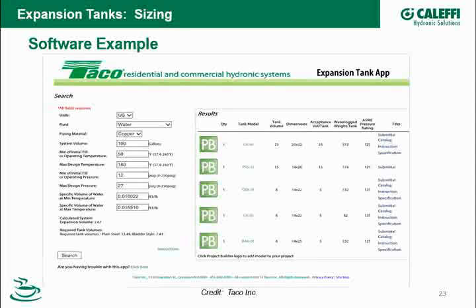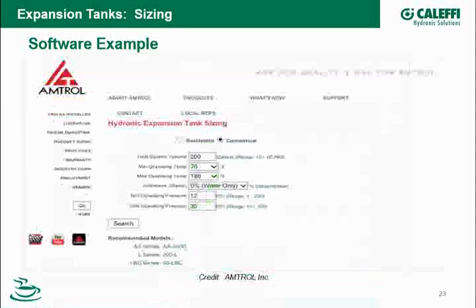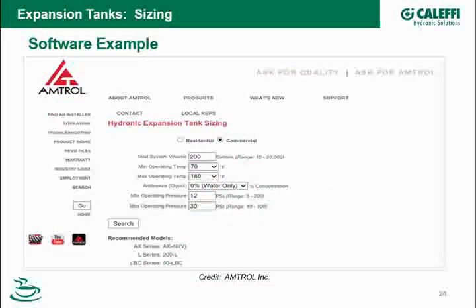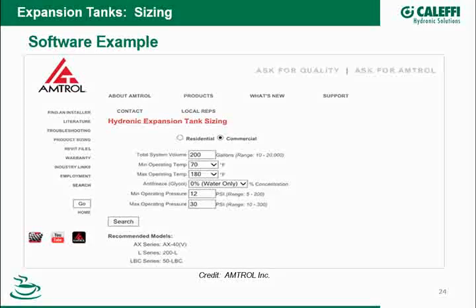Okay. Here's one from Amtrol. Bell & Gossett has one. I believe Wessels has one. So there's a lot of great resources out there to size the expansion tanks without having to actually go through doing the calculations longhand. And these software packages all have the information that we pretty much have been discussing so far. I need a total system volume, a minimum operating temperature, and a maximum operating temperature. We're going to talk in the future about the effects of glycol, but I also have to tell it what percentage of glycol is in there, and then a minimum operating pressure and a maximum operating pressure.